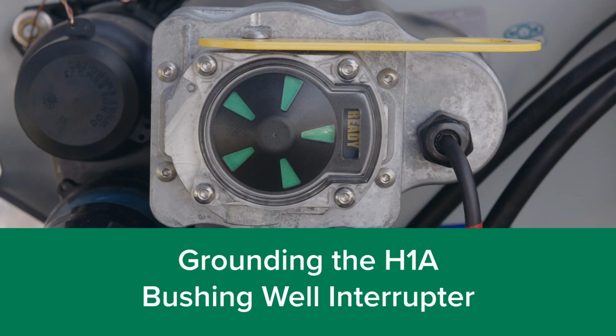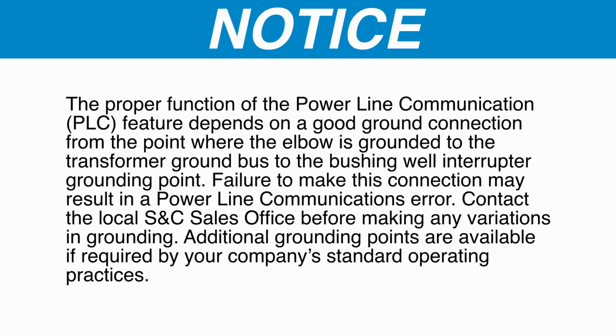Follow these steps to ground the H1A bushing well interrupter. Notice, the proper function of the power line communication (PLC) feature depends on a good ground connection from the point where the elbow is grounded to the transformer ground bus to the bushing well interrupter grounding point. Failure to make this connection may result in a power line communications error. Contact the local S&C sales office before making any variations in grounding. Additional grounding points are available if required by your company's standard operating practices.